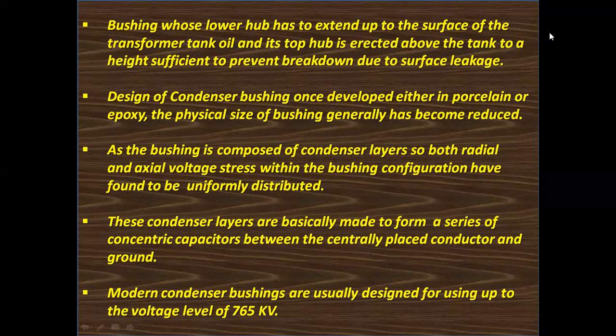As the bushing is composed of condenser layers, both radial and axial voltage stress within the bushing configuration have been found to be uniformly distributed. It's most important. These condenser layers are basically made to form a series of concentric capacitors between the centrally placed conductor and ground.